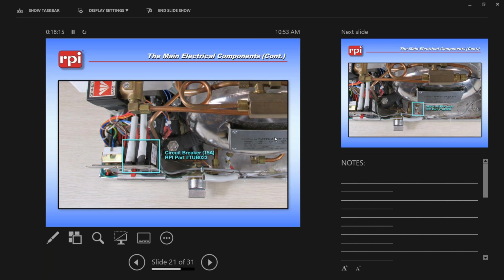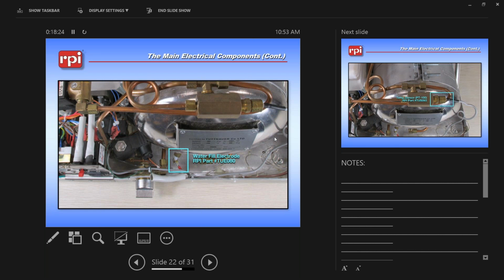Your circuit breaker in the back has the big red toggle on it. That is, of course, just like any other circuit breaker and how they function. Right in the back is your water fill electrode. These do not work as you might have seen on Midmark and things like that. They are not constantly monitored. So how Tuttnauer does it is they fill the chamber for a timed amount, and after that timed amount is completed, it will check to see if there's enough water. If this tells it that there is not, it will continue to run another timed cycle. So this will not cut out as soon as your unit is full of water.